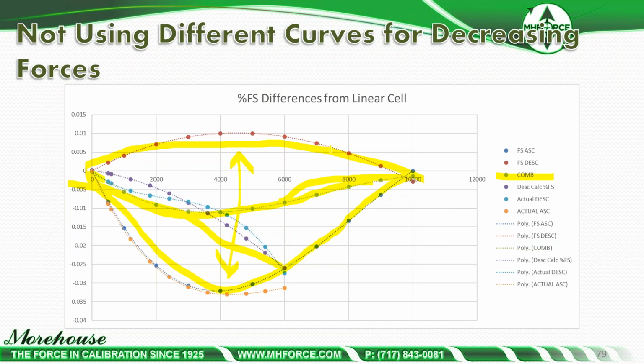The ascending curve can be used at any point in its range, right? You can go to 50% on an ascending curve and you can repeat all day long. That's the nature of the load cell. But when you're descending, the load cell has to be loaded to capacity to come back down. What people tend to do is they can do loops or anything else. But again, if you just go partially, you're going to get a different answer.